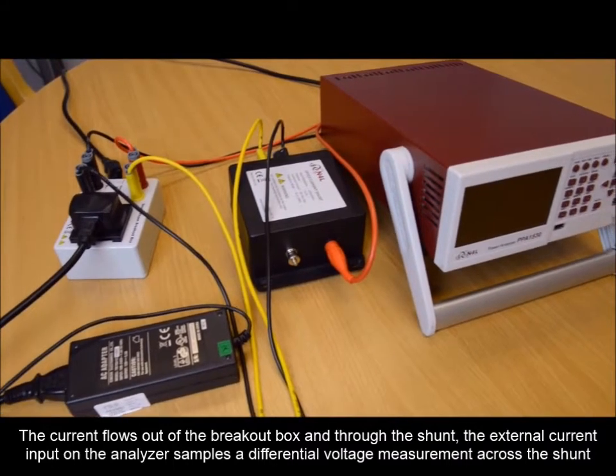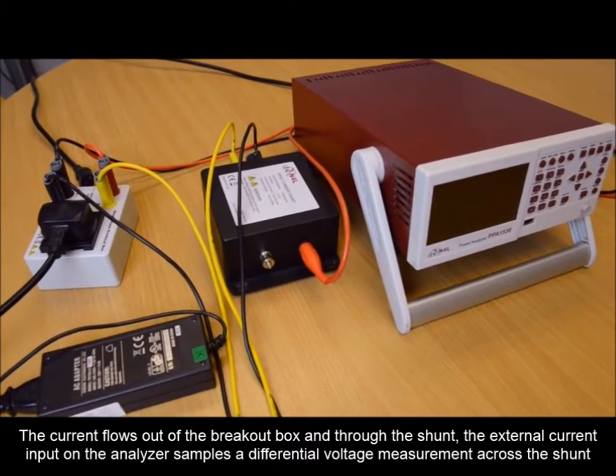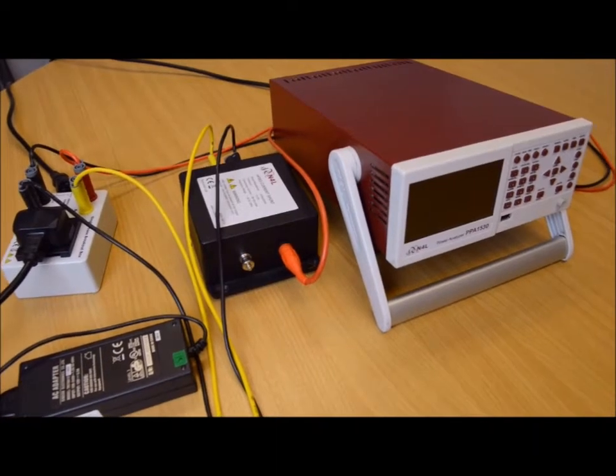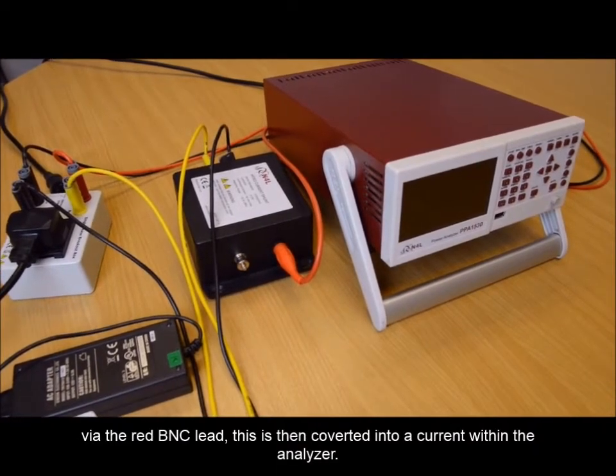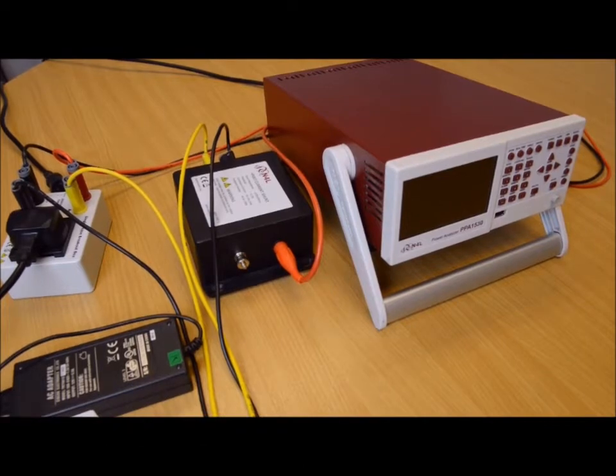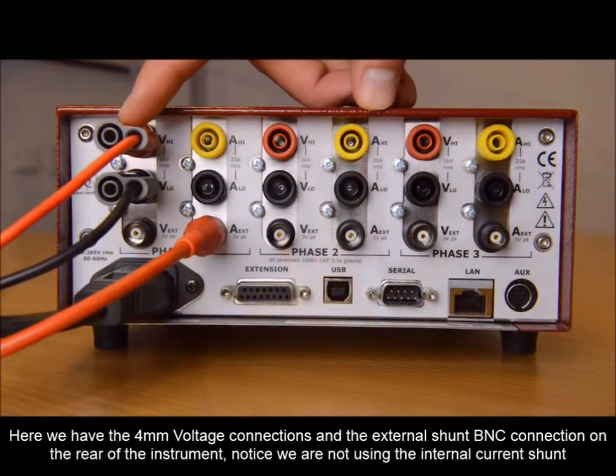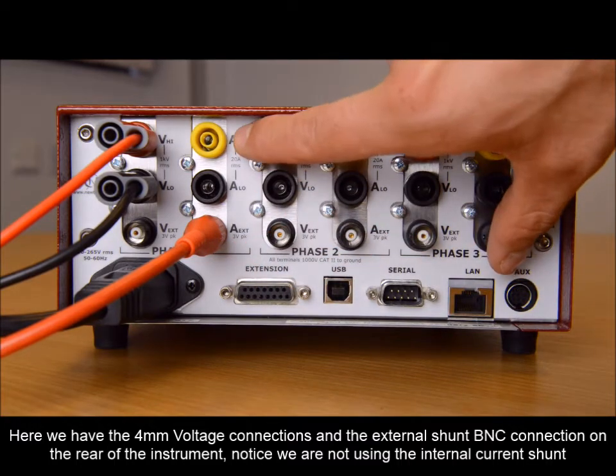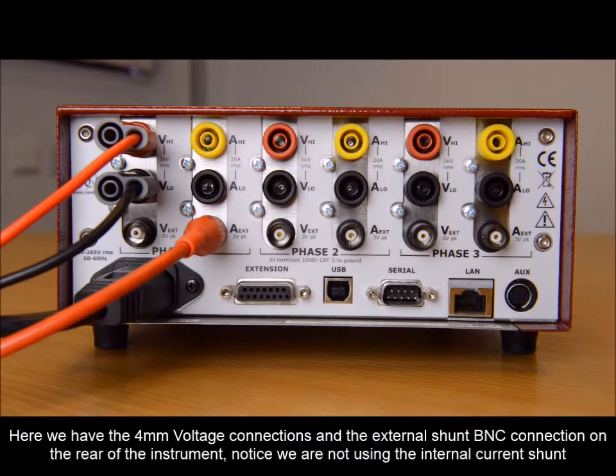The external current input on the analyzer samples the differential voltage measurements across the shunt by the red BNC lead. This is then converted into a current within the analyzer. Here we have the four millimeter voltage connections and the external shunt BNC connection on the rear of the instrument.